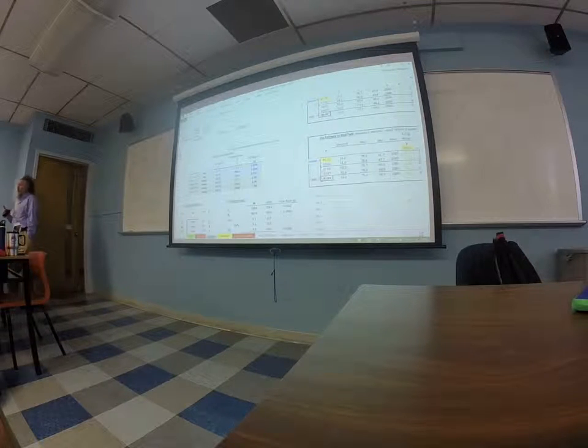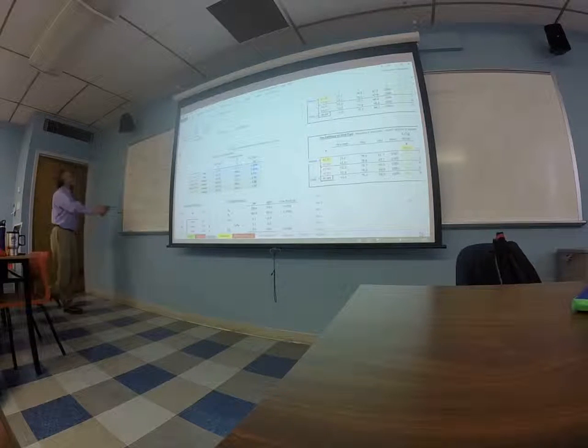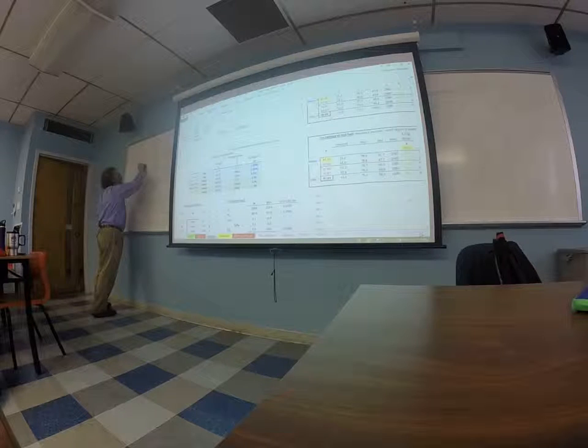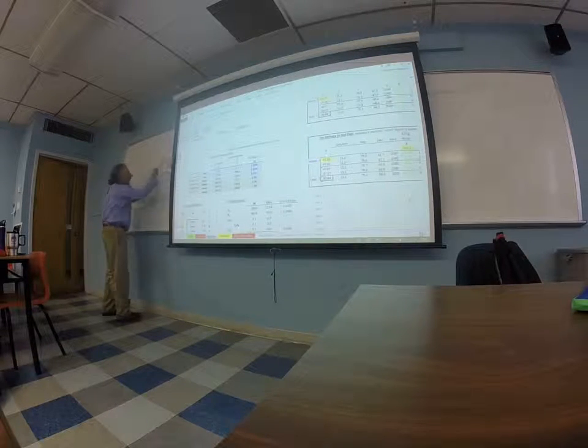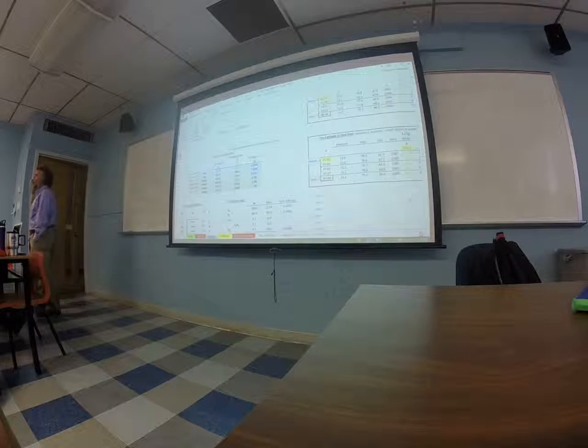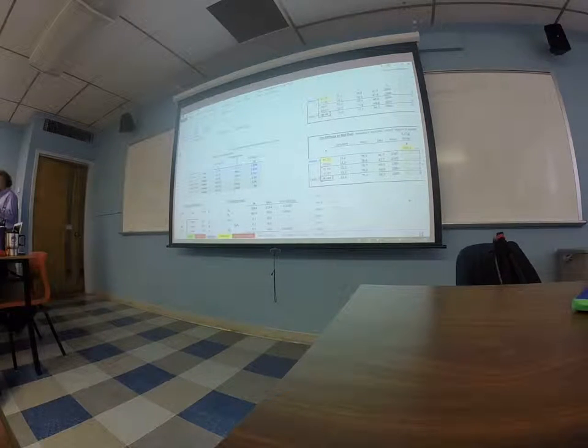So long as you don't use only the water in your calculation. If you're going to estimate the amount of propane based on the moisture content of the air and not on the overall enthalpies, because a group tried to calculate it just based on the change in moisture, the amount of water is so small and the error in the wet bulb temperature is so big that you would get wild variabilities in the amount of air. So that method is impossible. If you calculate the enthalpies, that's fine. You have all that information.